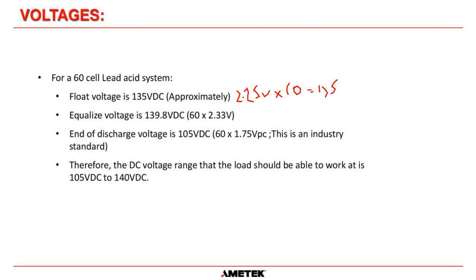Now for a vented lead acid system, you have to be able to put that system into equalize, and the equalize voltage is generally taken as 2.33 volts per cell. If you multiply 2.33 by 60, you get a voltage of 139.8 volts. And then in the design of your system, there has to be an end of discharge voltage, because there is a point where you don't want to discharge a lead acid battery past.